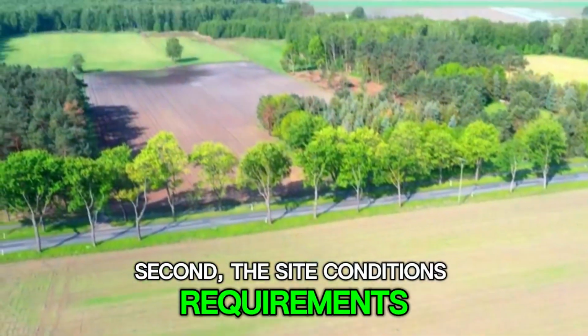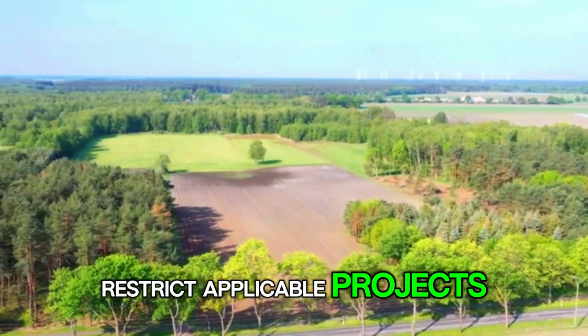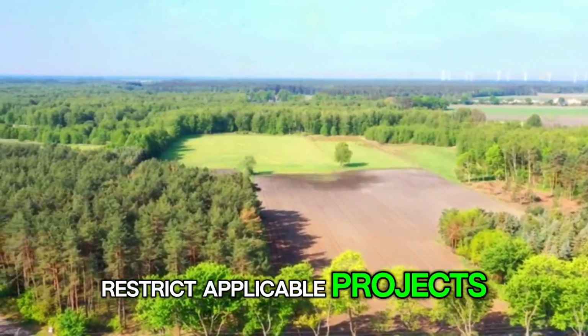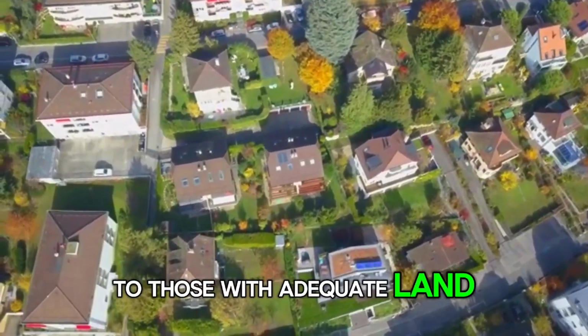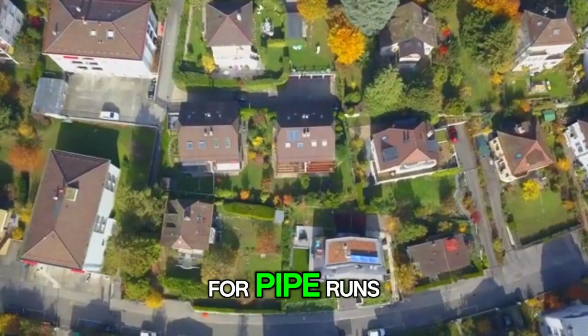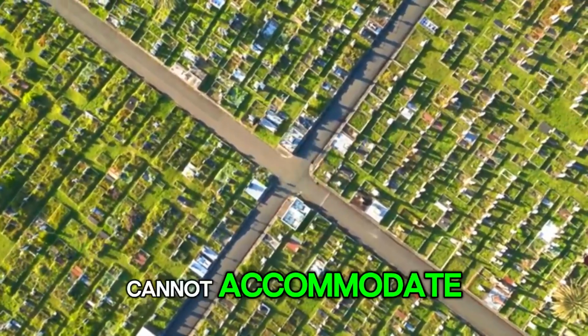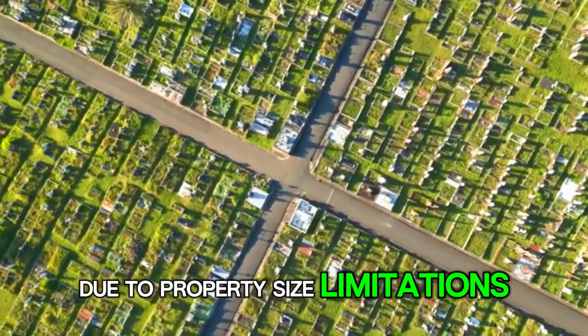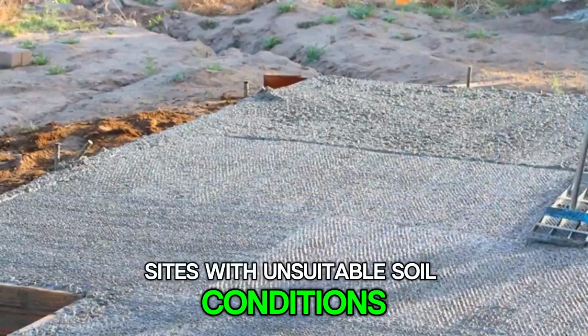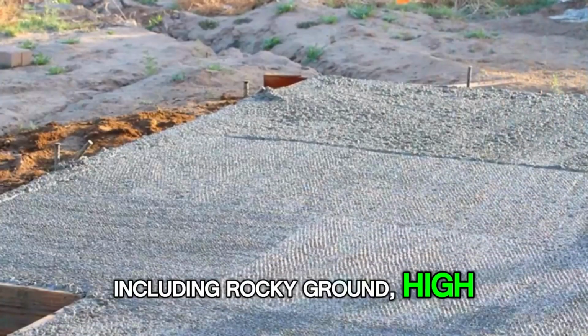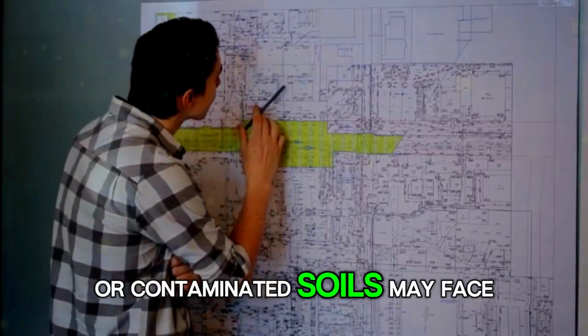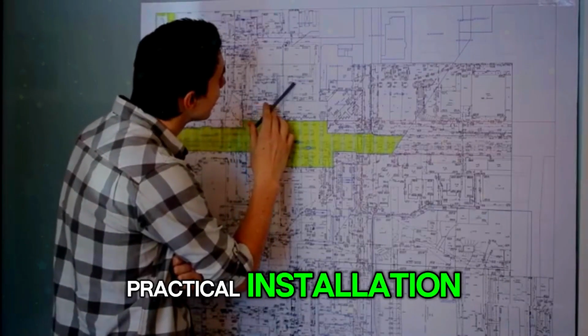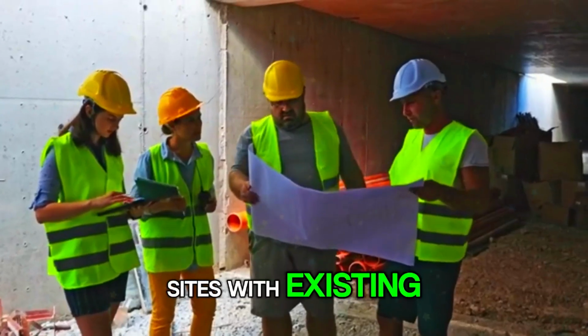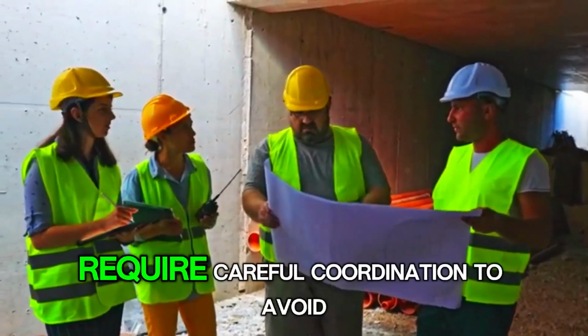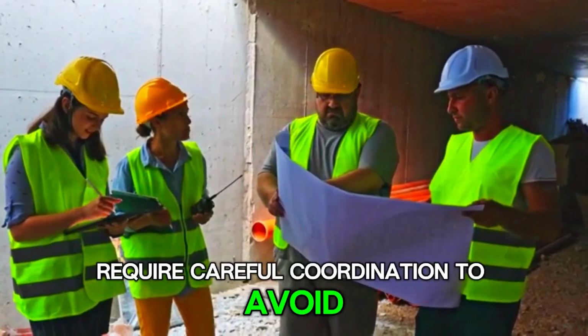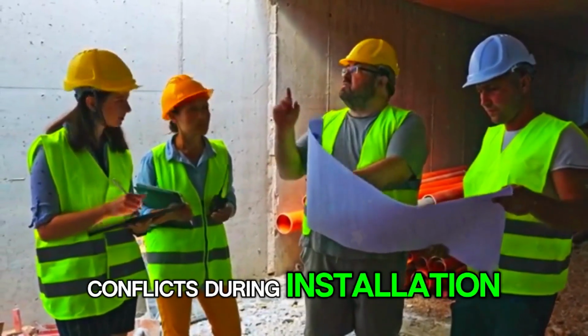Second, the site conditions requirements restrict applicable projects to those with adequate land area for pipe runs. Dense urban sites typically cannot accommodate earth tube installations due to property size limitations. Sites with unsuitable soil conditions, including rocky ground, high water tables, or contaminated soils, may face practical installation challenges. Sites with existing underground utilities require careful coordination to avoid conflicts during installation.